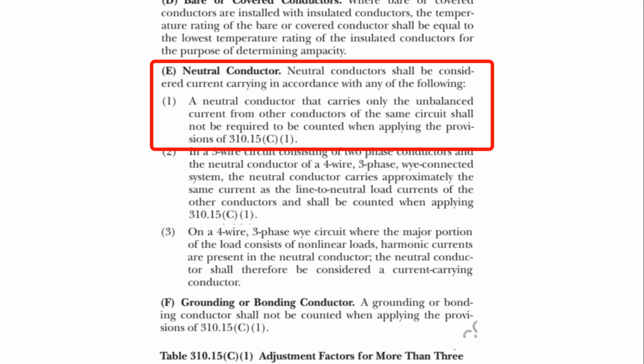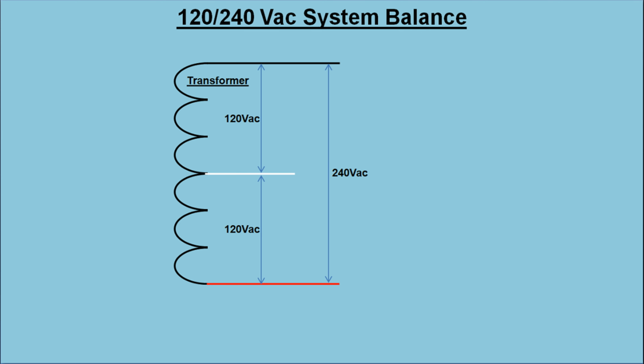310.15e1 says a neutral conductor that carries only the unbalanced current from other conductors of the same circuit shall not be required to be counted when applying the provisions of 310.15c1. The unbalanced current in a 120-240 volt system is the current that travels the neutral. That happens when there's more current flow on one of the hot lines than the other. If we had a perfectly balanced system, the neutral would carry 0 current because all of the current on the opposing 120 volt lines would create a 240 volt circuit.